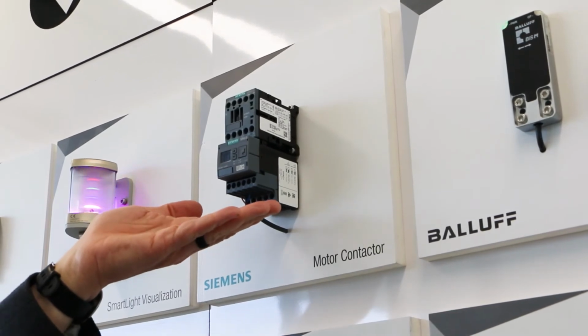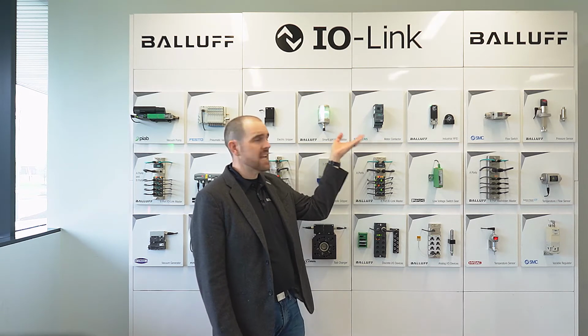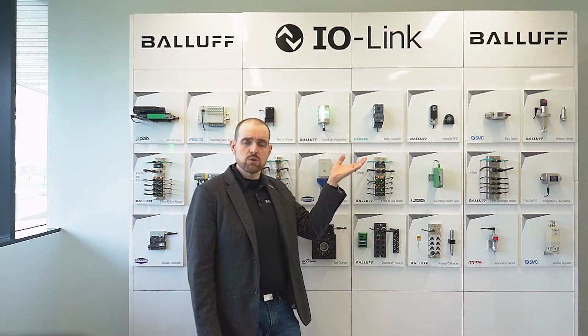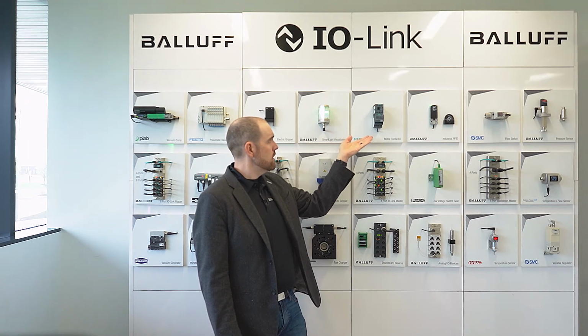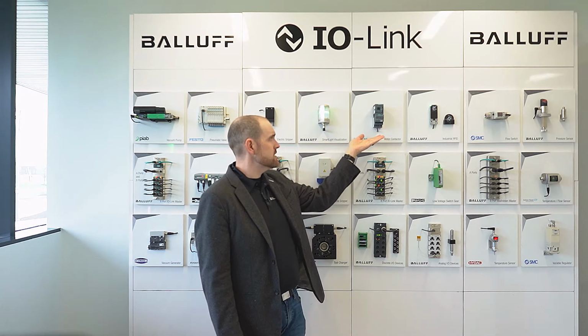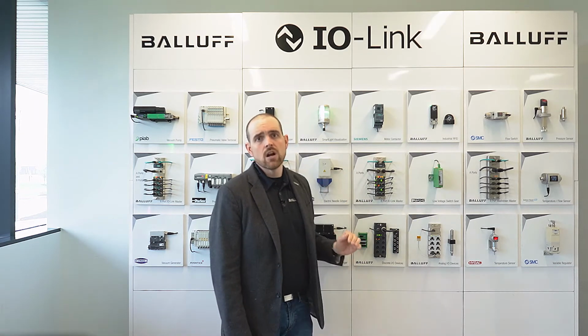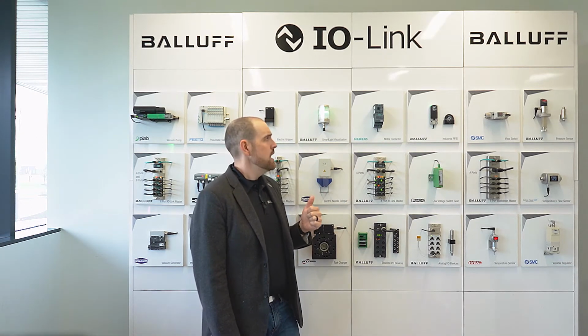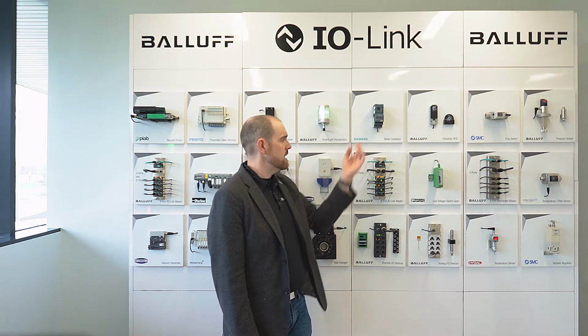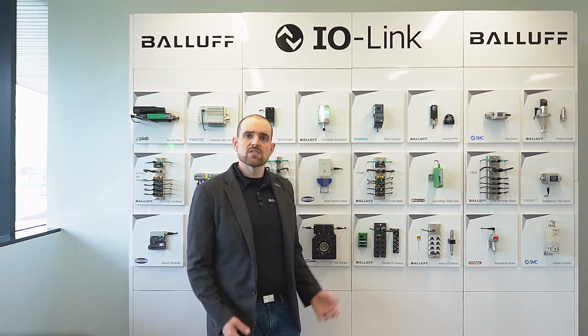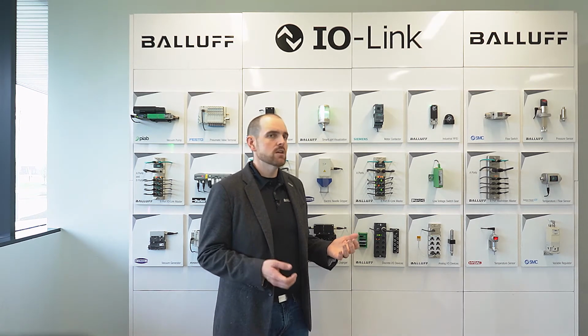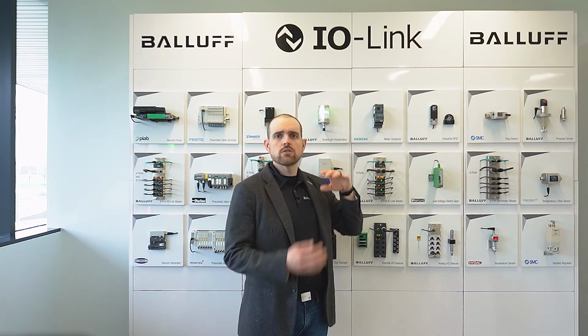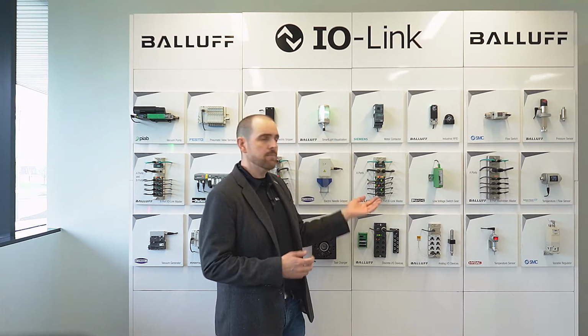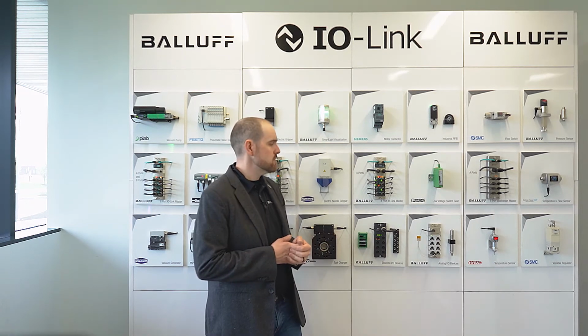Next, we have a Siemens motor contactor. I've had many customers talk to me about how much cost savings they got from this because of the IOLink control. They have the ability to see how many switch points, and control over lots of the settings of the motor contactor, and they can actually stack motor contactors here, all controlled with one IOLink port. That's a huge value for someone building an electrical cabinet, and there are manufacturers in the consortium, in the ecosystem, that make IP20 rack mount IO masters. So if you want to have that inside the control, you can have IP20 masters or an IP67 master to set up that architecture.